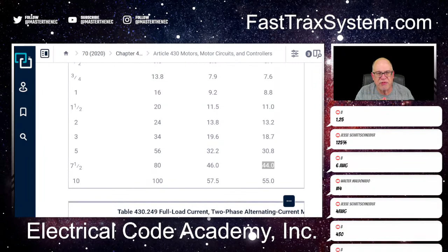I love testing you folks and letting you see. Where do you get that rule from? Because I want to tell you about motors for a second, some key things to remember. Since nobody's responding, I'll go on and do it anyway. When you have a single motor, you need to go to 430. There you go, Manuel, 430.22 for a single motor. If you have multiple motors, you go to 430.24. For short circuit ground fault protection for motors, you go to 430.52. So that's where you go for that.